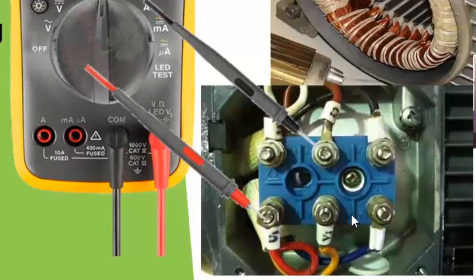So if you have turn to turn short or short between the windings, if you test between U1 and V1, you may have a beep or it may show continuity. That is to show that there is a short between those phases, between U and V. If it is between V1 and W1, if there is a beep, it shows that there is a short between the V phase and the W phase windings. Those are undesirable conditions.